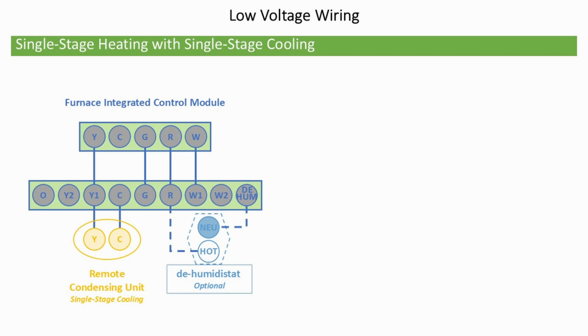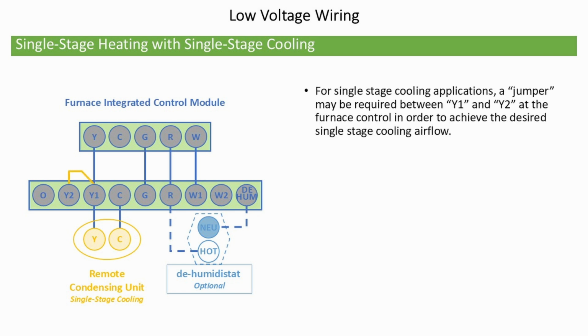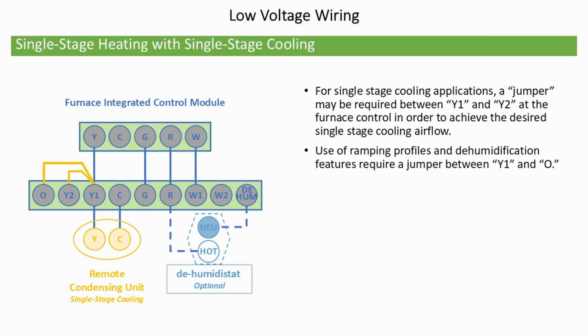Low voltage wiring, single stage heating with single stage cooling. Here's a wiring diagram showing the connections needed between the thermostat and the furnace integrated control module. For single-stage cooling applications, a jumper wire may be required between Y1 and Y2 at the furnace control in order to get the desired single-stage cooling airflow. Use of ramping profiles and dehumidification features requires a jumper between Y1 and O.